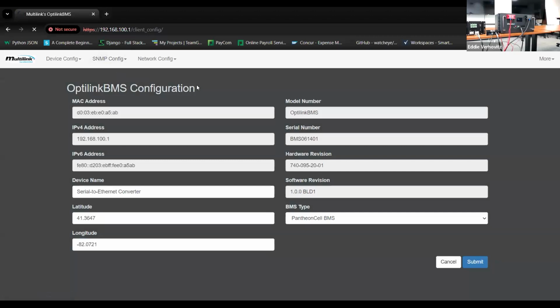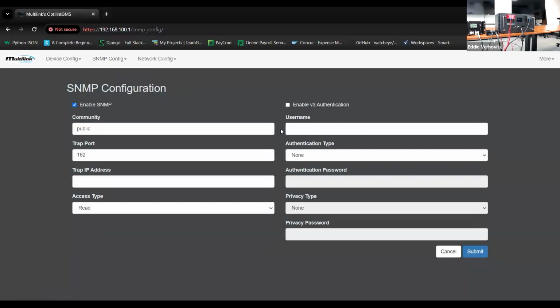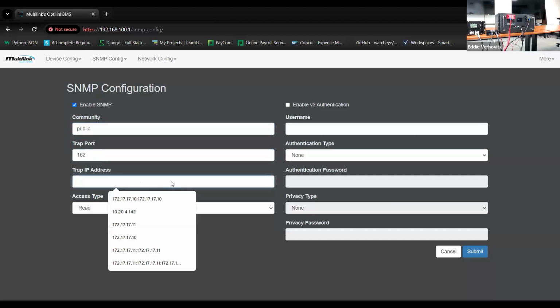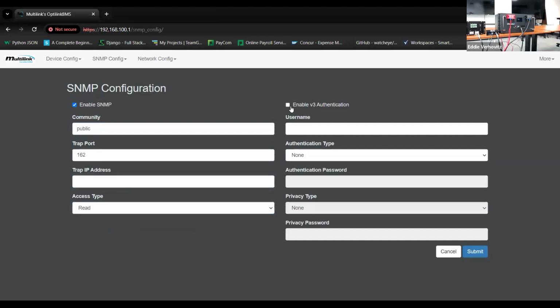Moving on to the SNMP configuration page—in most scenarios, power supplies, Optilink BMS, and remote power managers that we offer for Multilink utilize SNMP to provide remote information using UDP access. With this SNMP configuration page, you can provide a community string, which acts as a password to the device itself. You can set up the trap port and trap IP address, which is the receiver of notifications from the power supply, as well as access type, read and write. And if you have version 3 available to use, you can enable or disable that information from here and fill in the credentials as needed.